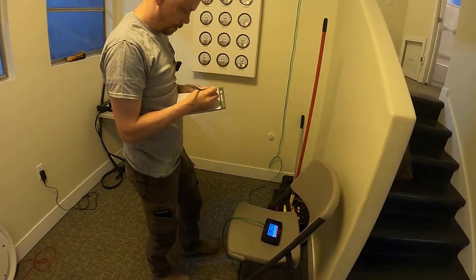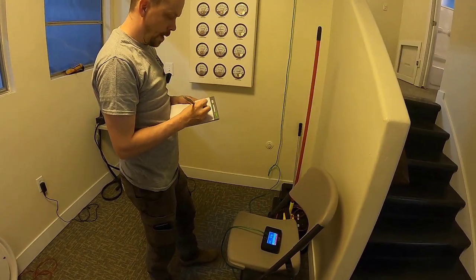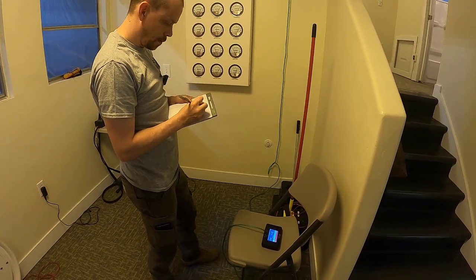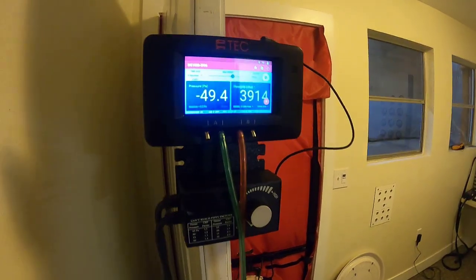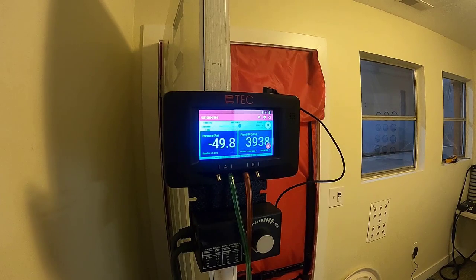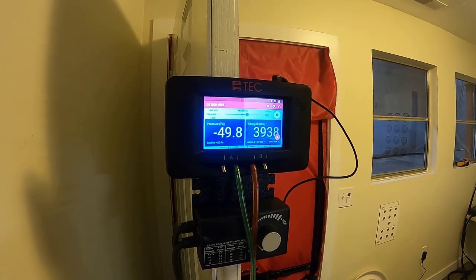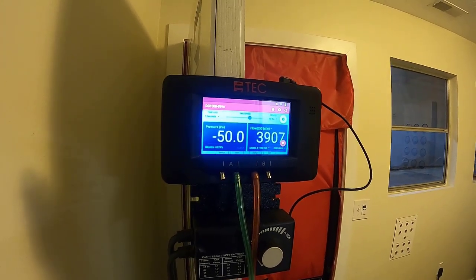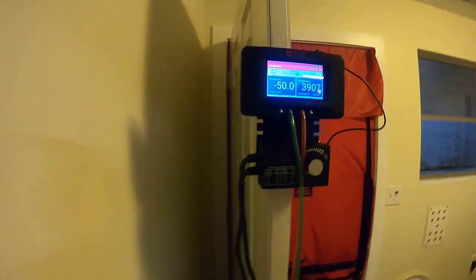The Home Performance Diagnostic Guidebook says to get a pressure difference of at least 6 pascals when you're doing this test, but I found the RedCalc calculator, which I'm going to show you in a minute, works better when you get a pressure difference of at least 10 pascals.